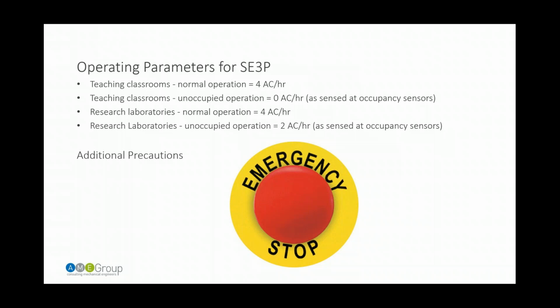And we've got max air changes at about 8 air changes. And so if anybody has had a spill or thinks that they've had a spill and they run out of the lab and they press that button, then it's just going to ramp everything up to 100% airflow, even if the Aircuity system hasn't measured that room yet. Everything's going to go into an emergency mode. So I think precautions like that need to be considered as well when we're looking at these systems, again, because they don't react quickly. They take measurements pretty periodically. So we just need to make sure that those safeties are still in place.